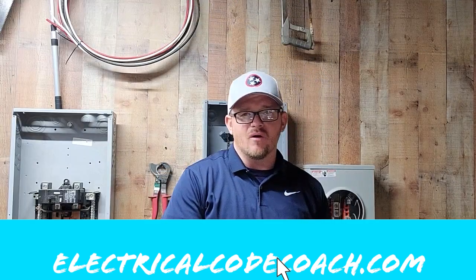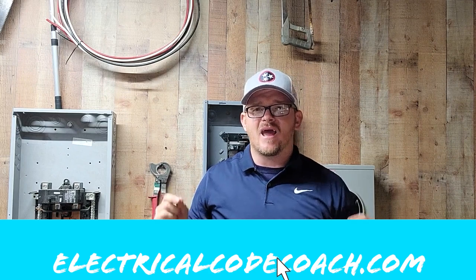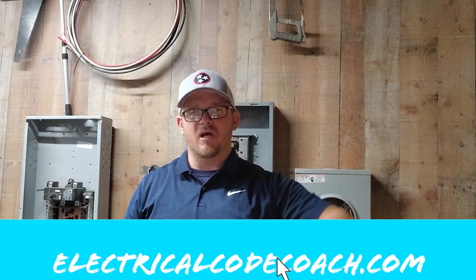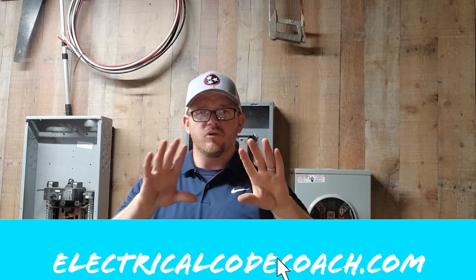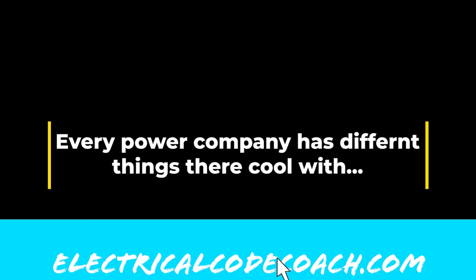Really excited about today's video. Recently on a job I was shocked by 580 volts on a job that didn't even have the service connected. I was out on a temporary pole situation that was going to be used as a permanent pole. In this jurisdiction the utility actually allows you to mount the equipment right to their pole, which is a new situation for me because where I normally work all of my power companies will not allow you to mount anything to their poles.